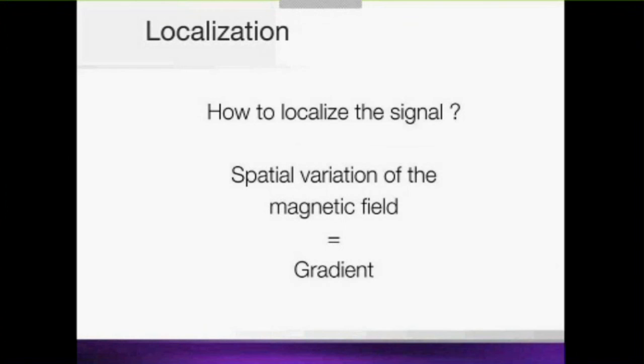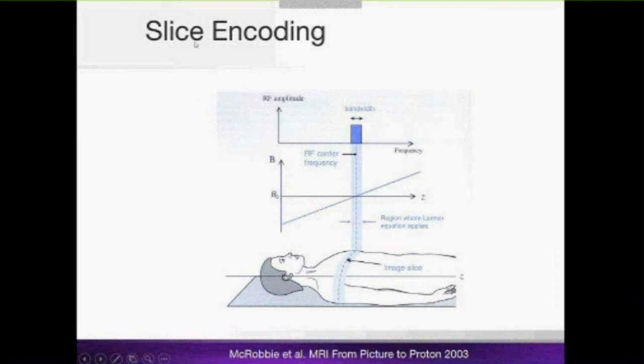We still have a problem: we have understood how to create an echo and receive it in the coil, but the coil receives signal from the whole head at once. How do we localize the signal — how do we know it comes from the tip of the nose rather than the middle of the ventricles? For this we use a gradient, which is a deliberate spatial variation in the magnetic field. There are three types of gradient: the slice-encoding gradient, the frequency-encoding gradient, and the phase-encoding gradient.